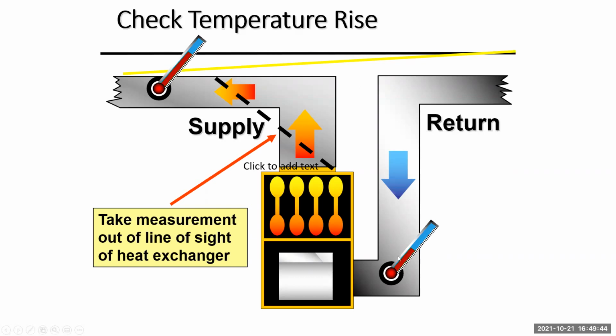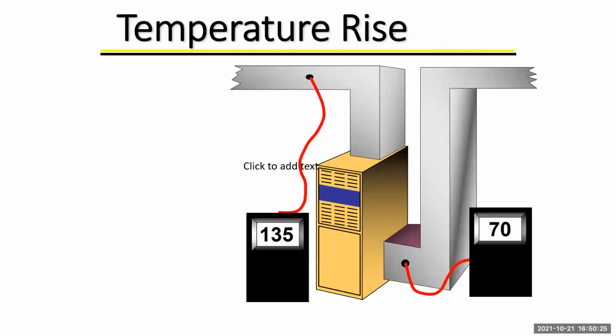When we're checking our return, we want to get down as low on that return and as close to that blower as possible. You don't want to grab a return up in the return trunk or clear up against the ceiling or something. Get down closer towards the bottom. When you're checking your supply, get away from your plenum and your takeoff. Get up and around the corner 3-4 feet and then grab a temperature there. And if you don't believe me, try it one day. If you've never done it, go right above your coil and then go over, and you're probably going to have an 8 to 10 degrees difference. So get up and around the corner, and that's your supply. Your supply minus your return is your temperature rise.